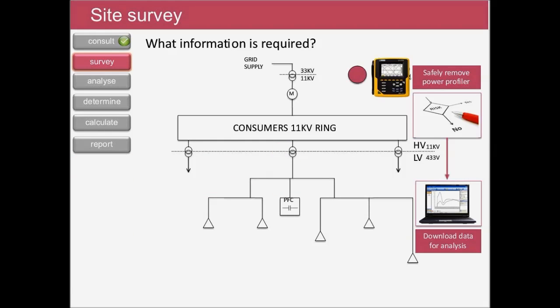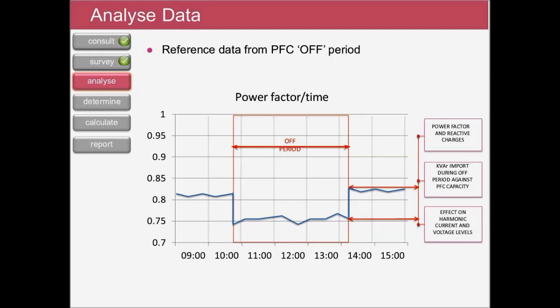So following the agreed monitoring period, the power profiler can then be removed and the data downloaded for analysis. Another advantage of using the power quality analyzer is its ability to properly measure the reactive power and any harmonic interaction between existing power factor correction equipment and harmonic generating loads on the LV network. This is an increasingly common problem and one that's frequently overlooked, but easily identified if the study is correctly undertaken.